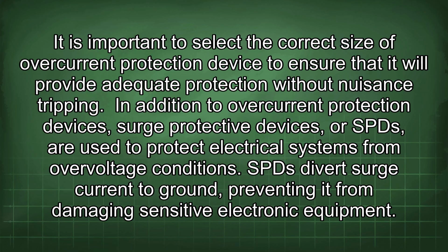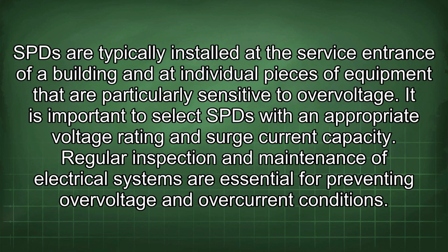In addition to overcurrent protection devices, surge protective devices, or SPDs, are used to protect electrical systems from overvoltage conditions. An SPD diverts surge current to ground, preventing it from damaging sensitive electronic equipment. SPDs are typically installed at the service entrance of a building and at individual pieces of equipment that are particularly sensitive to overvoltage. It is important to select SPDs with an appropriate voltage rating and surge current capacity.